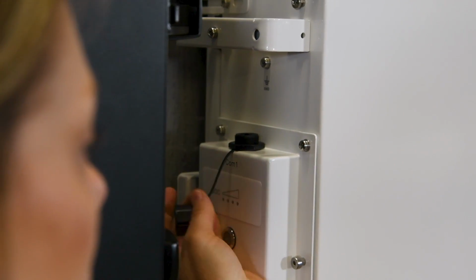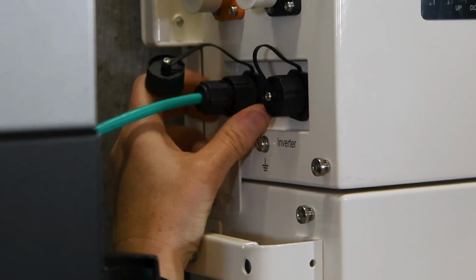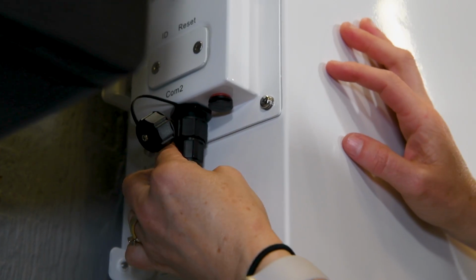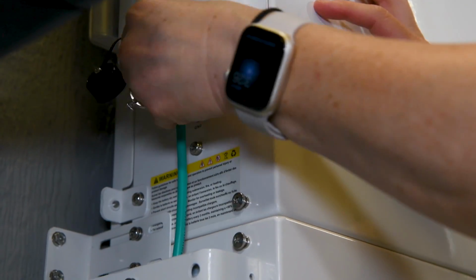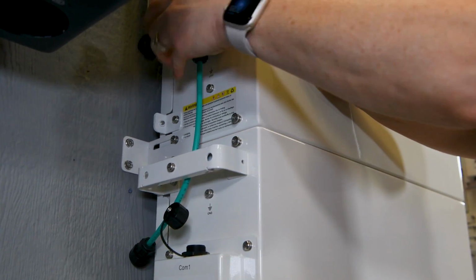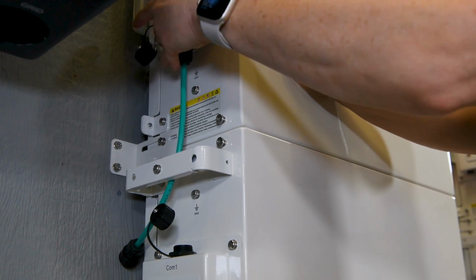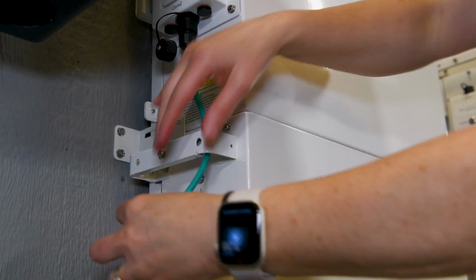Open this port as well as COM port 1 on the first battery module and plug in our communications cable into both, screwing them in until they are snug. Then move down to COM port 2 on the first battery module.